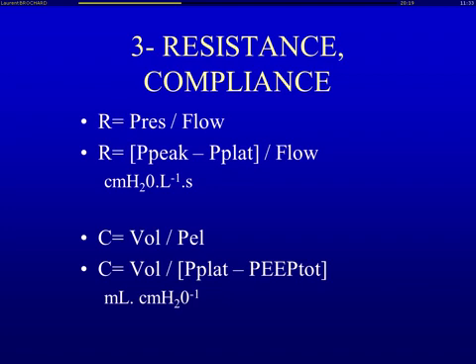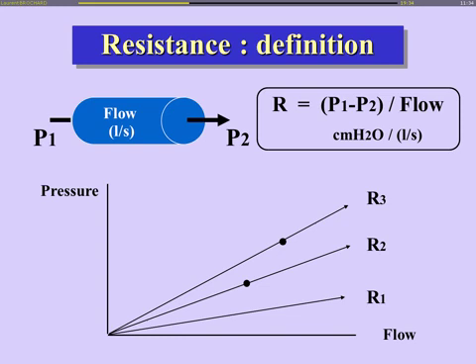From this equation of motion you can calculate resistance and compliance. Resistance is calculated as the difference between peak pressure and plateau pressure divided by the mean inspiratory flow. Compliance is calculated as the volume put into the system divided by the elastic pressure, which is the plateau minus the PEEP. If you don't remember how to do this, modern ventilators perform these calculations for you. One difficulty for the ventilator is intrinsic PEEP, which can mislead these calculations.